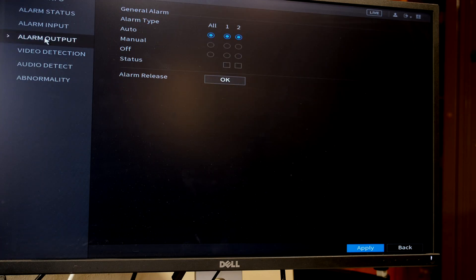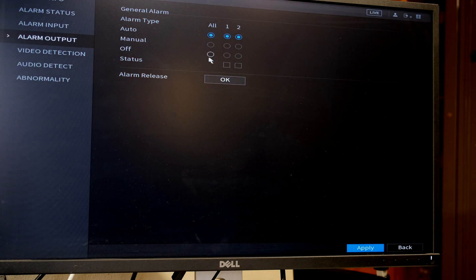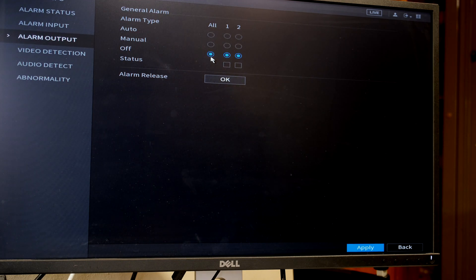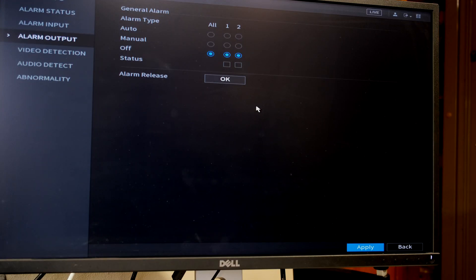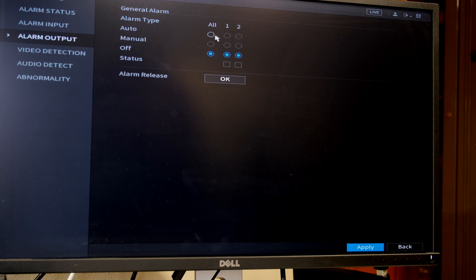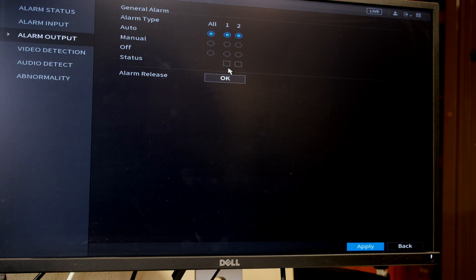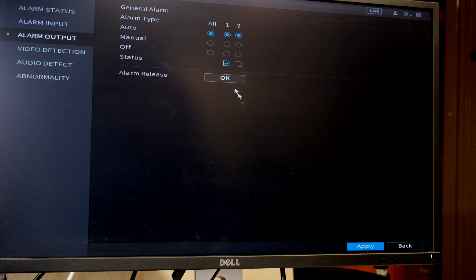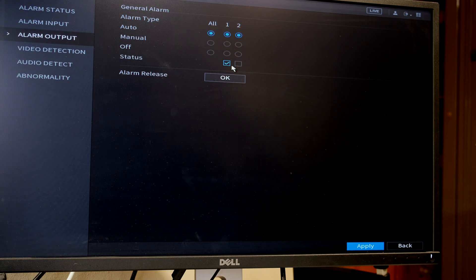Now there's an alarm output tab here. If this is in the off position you are overriding and switching off your alarm outputs - you are literally disconnecting those relays. So make sure yours is on the auto position. Over here the status tells you the current position of the relay. So if I trigger an alarm now and apply, you can see that output one is now activated. You can see the status of your alarm outputs if you need to. This is sufficient for the alarm condition to work.